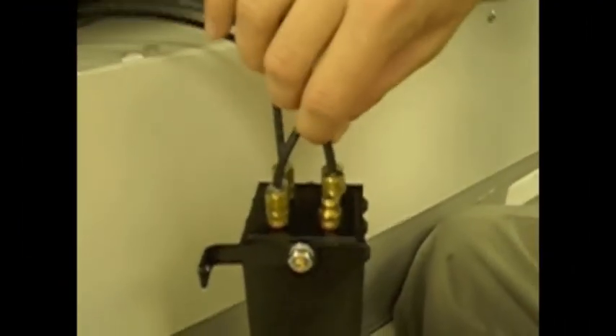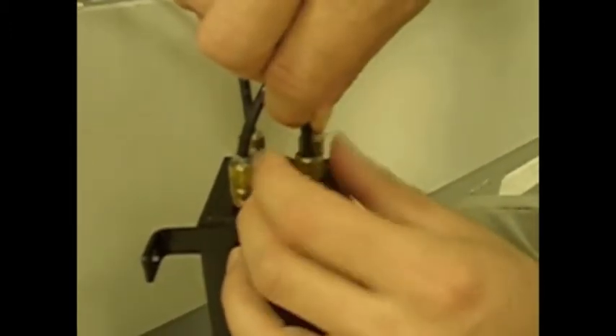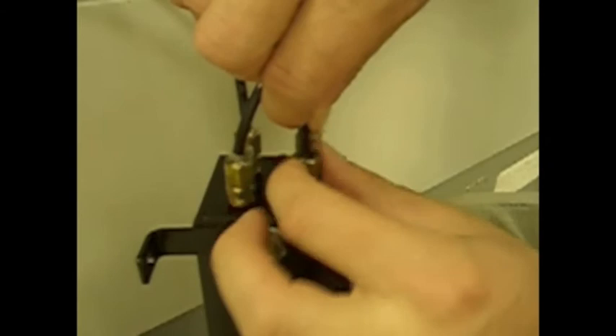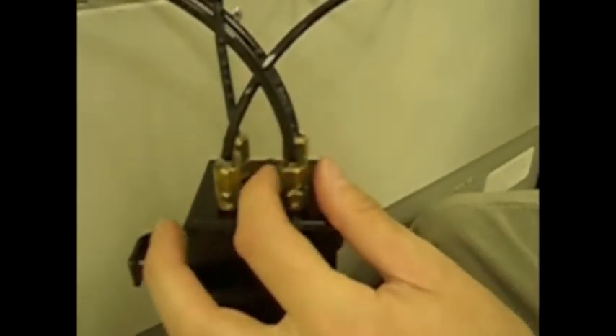Replace the hydraulic line fitting on the now recharged cylinder. Tighten the compression nut and wipe away any excess fluid. Do not over tighten the nut. One quarter turn after finger tight is maximum.